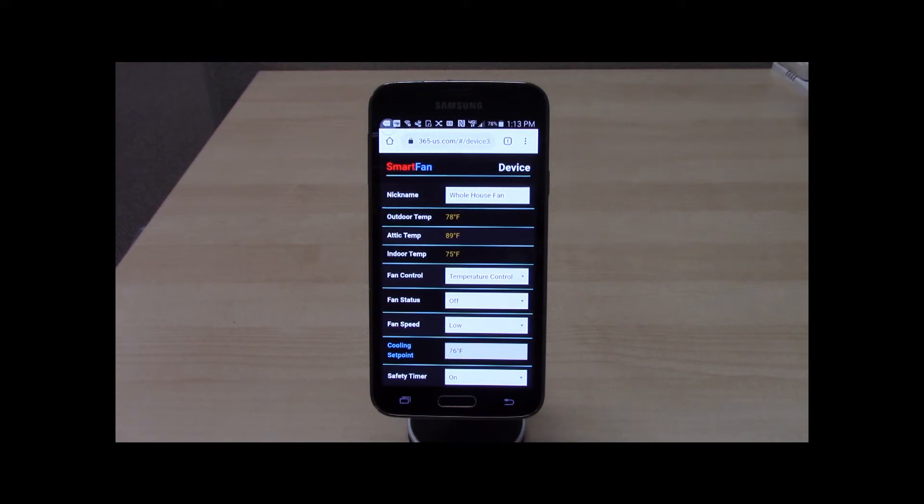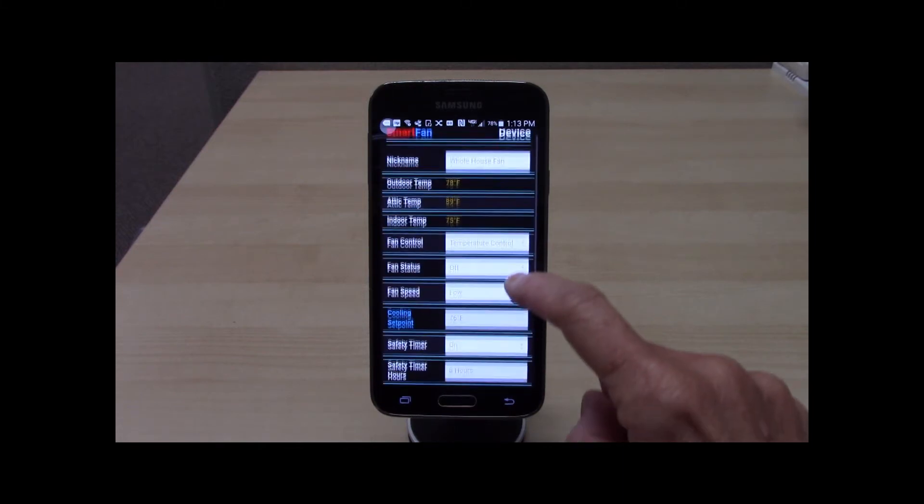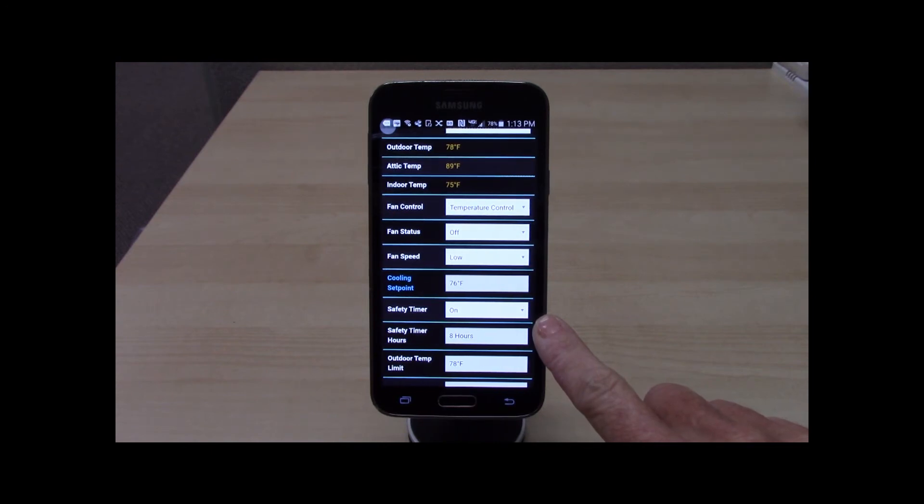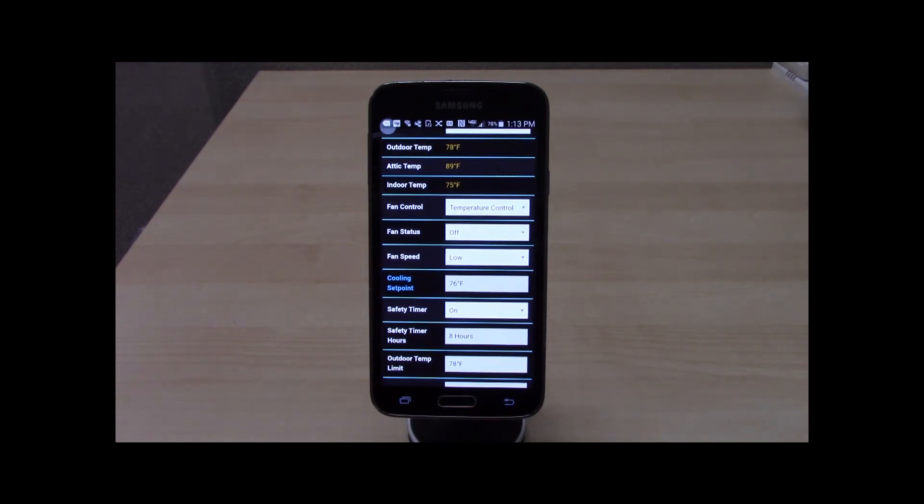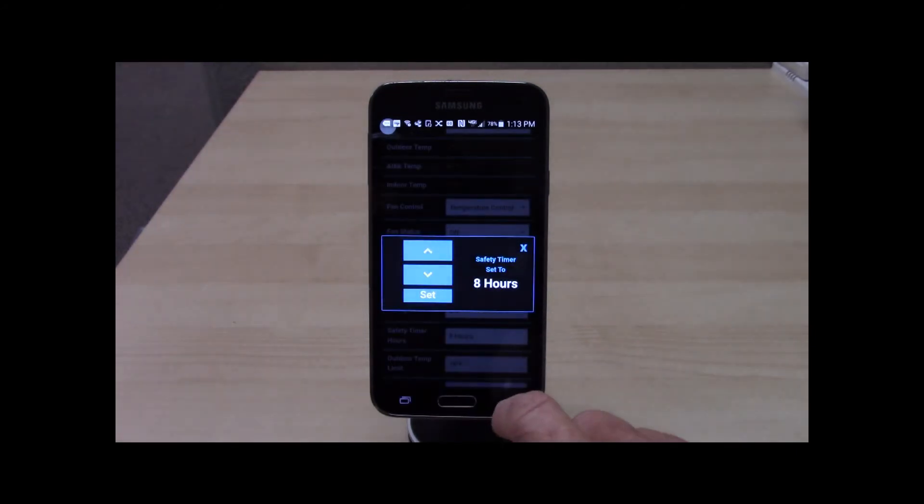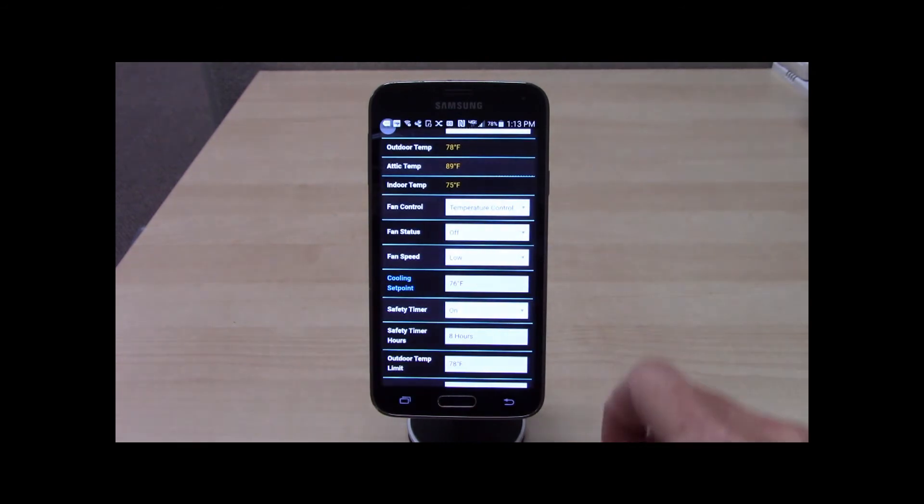The fan, when turned on, will cool the home to the comfort temperature set. A safety feature used in temperature control is the safety timer that automatically turns the fan off the following morning after a set number of hours, in case the homeowner forgets. The safety timer can be set from 1 to 12 hours.